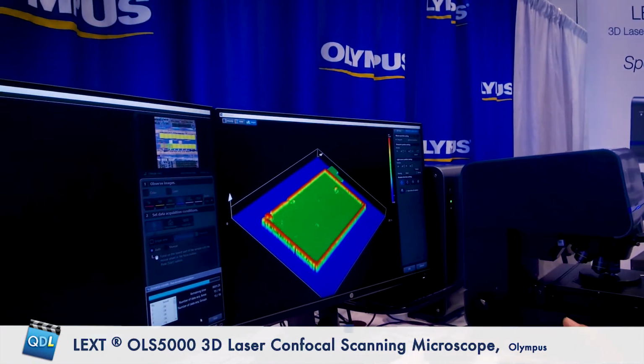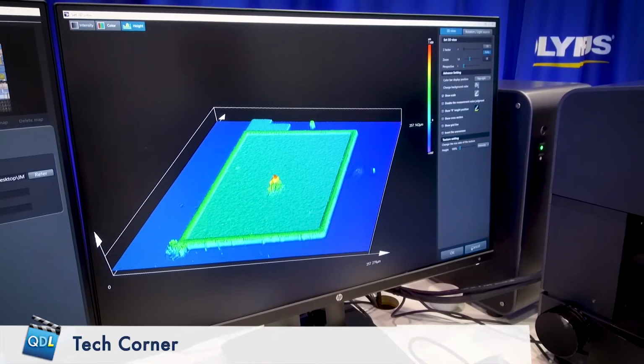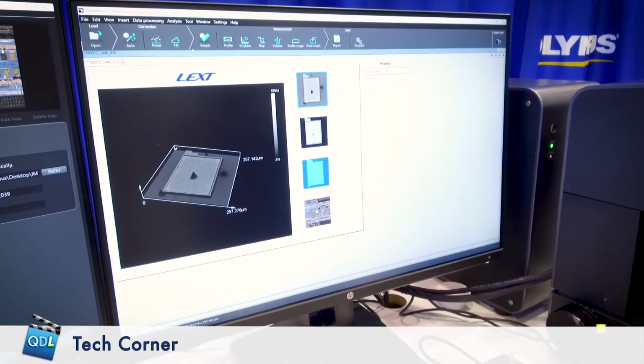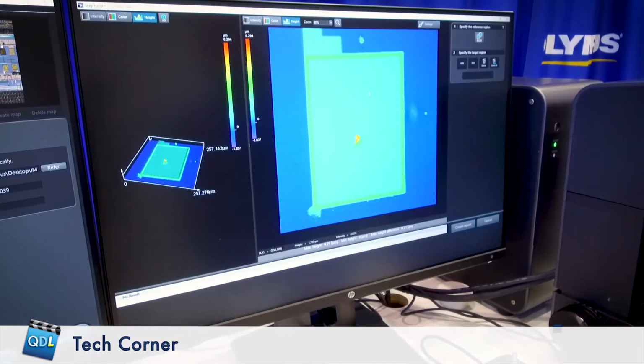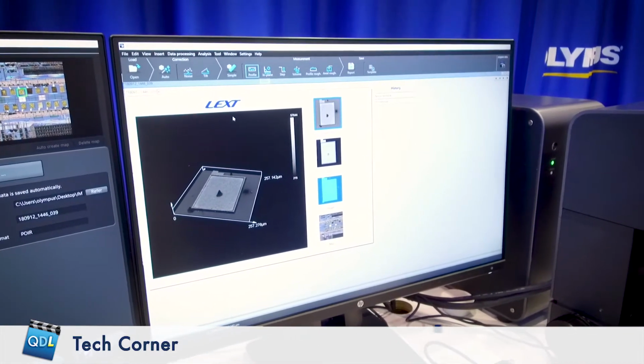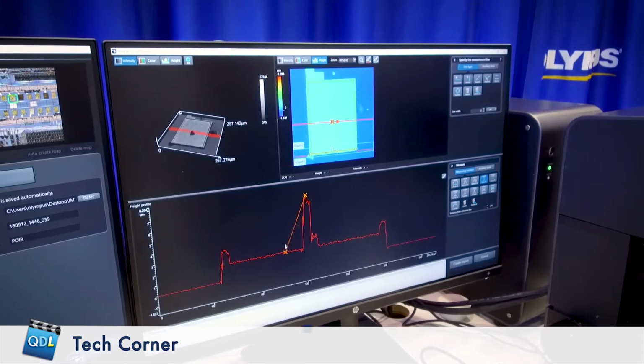And what's on the right-hand screen here? Here we're showing the analysis window. As it's doing the acquisition, you have some time, and you want to think about how to look at the data and build the best analysis recipe. This is a separate program, which improves the whole operation efficiency. For example, you ask, do I have some defects here, or a scratch here? I look at the different channels. Now I'm looking at the color channel, or the laser intensity channel, and figure out what I should do. And you can do this at the same time it's actually taking the data.